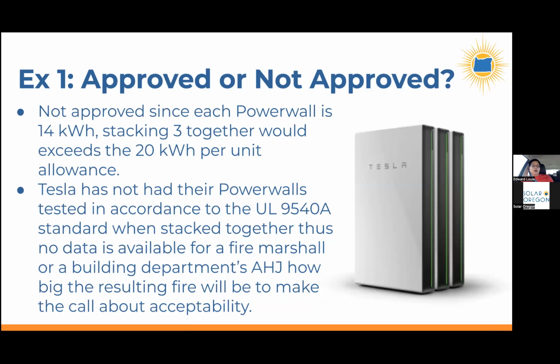And so here are some examples now. Tesla, for example, one of the most famous home energy storage systems, in their marketing material, they show a picture of 3 of their Tesla Powerwalls stacked together. Under the new rules, this is technically not allowed, because each Powerwall is 14 kilowatt hours. You stack 3 of them together, you end up with more than 20 kilowatt hours per unit, which is over the allowance. And then also, Tesla has not actually tested their Powerwall with 3 of them stacked together to the UL 9540A test. Sure, if you look at the Tesla specs, they list that their battery is UL 9540 certified, but that's only with 1 Powerwall. And as shown in the other slides, when you start stacking 2 or 3 of them together, that's a new configuration. And so a new configuration requires its own separate UL 9540A test. And so that data is not available.